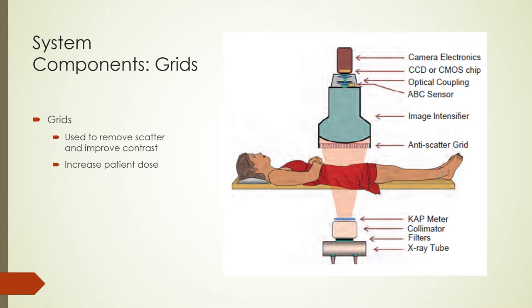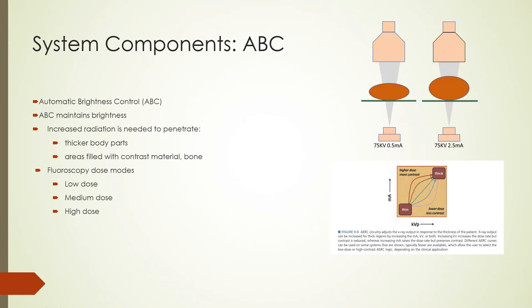An important function of fluoroscopy imaging is maintaining image brightness and signal-to-noise ratio for different anatomies or thicknesses. This is accomplished by an automatic brightness control or ABC system. ABC ensures that more radiation is used to penetrate thicker or denser anatomy and less radiation is used for thinner anatomy — similar to the AEC system in general radiography. A sensor on the output side of the image intensifier detects light output and compares it to a reference. Differences trigger a feedback circuit that causes the generator to adjust kV, mA, or both. Predetermined curves can be used to maintain image brightness by increasing kV, mA, or both.